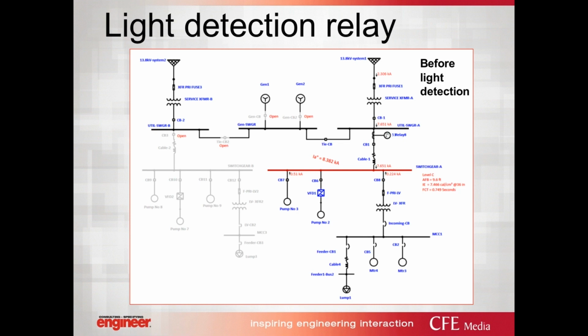I have another simulation here for you. Let's assume we are trying to apply this to our 4.16 kV switchgear A, and we're trying to look at how much impact it's going to have. At this point, before the light detection approach, if there is an arc fault at switchgear A, I will have incident energy of around 7.5 calories per centimeter squared.